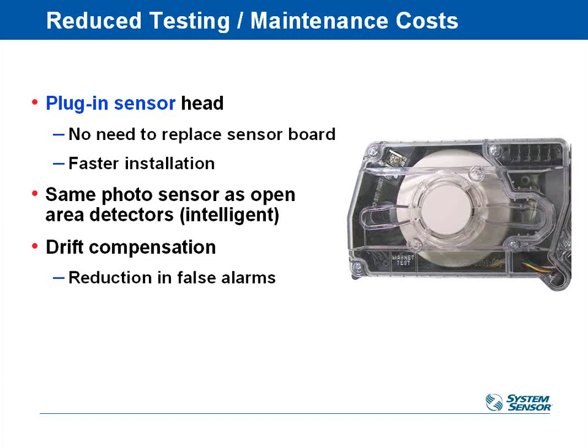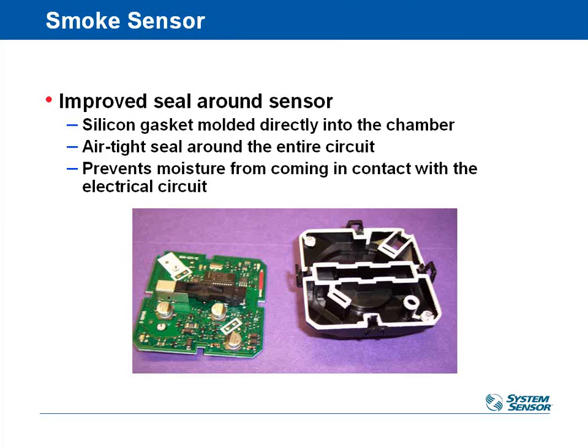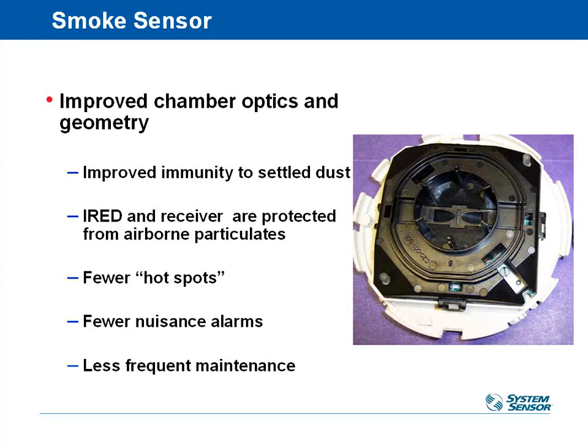These detector heads that are used are the exact same ones that System Sensor uses for their space detection products. So that helps out with manufacturing volume because there's a lot of stuff that goes in spaces, obviously. And it also makes it easier for you to replace them if you're a building owner and you have some of these on the shelf for your space and you need to replace one in a duct. It's quite easy to do. Same technology. They are sealed, obviously. It's a silicone gasket that seals around the circuit board, preventing moisture from getting into the electrical circuit.